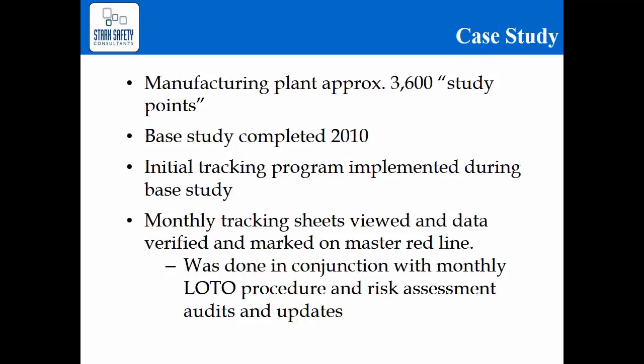Now we want to look at a case study from a facility where we performed an arc flash analysis back in 2010. It was a manufacturing plant that had approximately 3,600 study points — pieces of equipment where evaluation needed to be done from an arc flash study perspective. This was an ongoing facility evaluation where right from the beginning we had a tracking program in place that was started during the base study. It was a periodic tracking as well as updating of the one-line. Looking at since 2010 — this is 2015 now — we're actually on arc flash study revision 7.